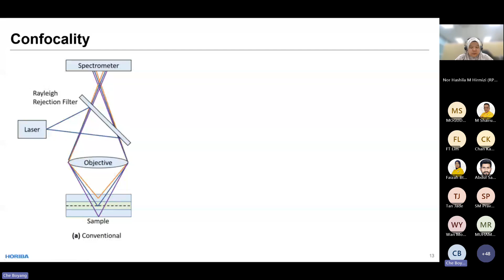So to solve this problem, we add a confocal pinhole just in front of the spectrometer. This is a very small hole, and you will be able to reduce and control its size. By reducing the size of this hole, it will start to block the signal coming from the top or bottom layer, because only the signal from the focal plane will go through the middle of this hole. So by reducing the size of this pinhole, you block that noise. By doing this, we get less intensity, but we get a purer signal from your area of interest.